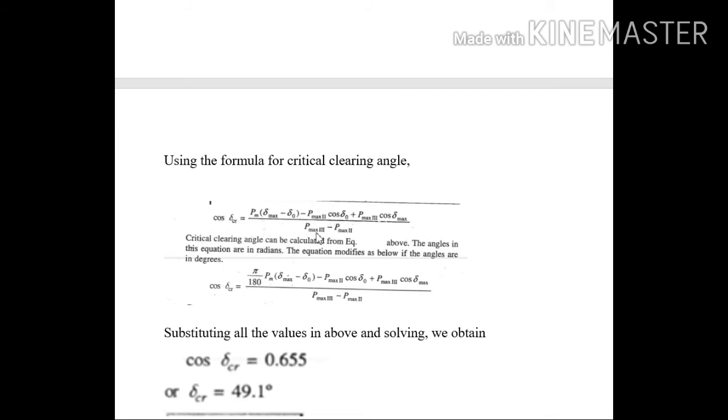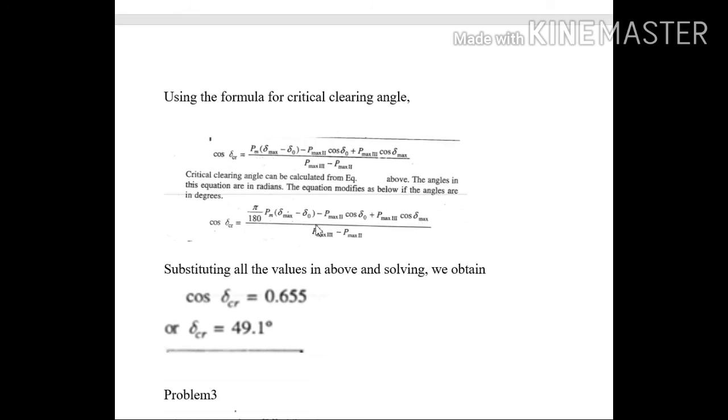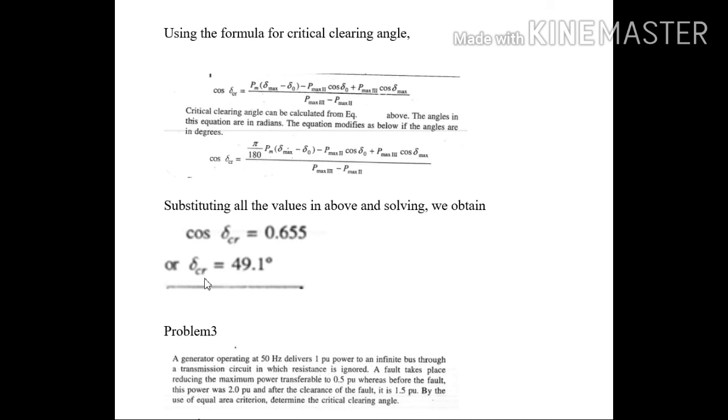Then using the formula for critical clearing angle, the expression that we discussed in our formula sheet slide. Substitute all the values. Now you are knowing all the values. If I want in degrees, use this formula. Substituting all the values in this formula, we got the expression as cos delta CR equals 0.655, and hence the critical clearing angle in degrees will be 49.1 degrees.